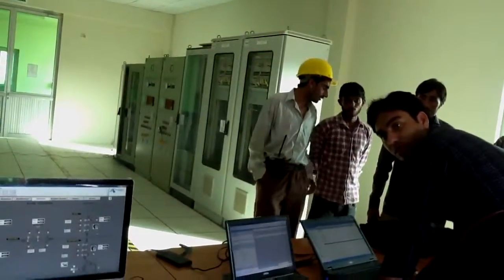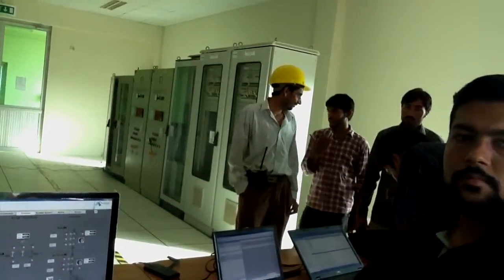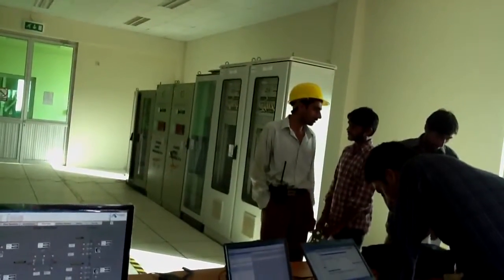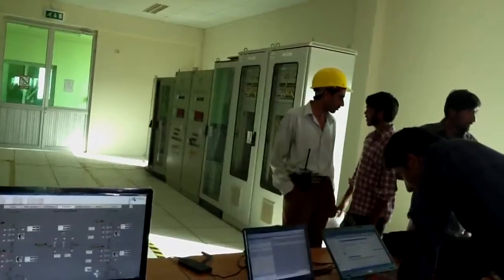And there are three main protocols which we are using. These are the latest, state-of-the-art protocols. IEC 61850, on which all peripherals are connected through an optical fiber system in a ring configuration. The beauty of the ring configuration is this: if one side is broken, then our system will run without any interruption. It's called self-healing. Basically, it's a self-healing process.